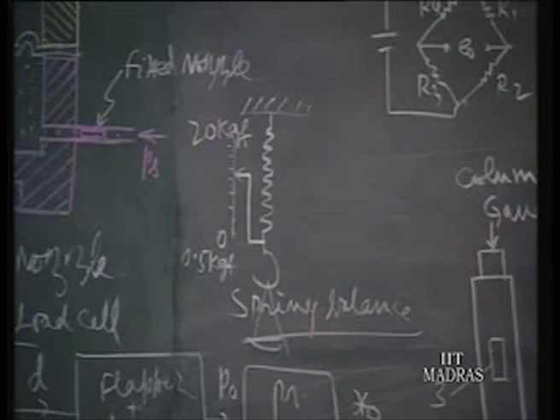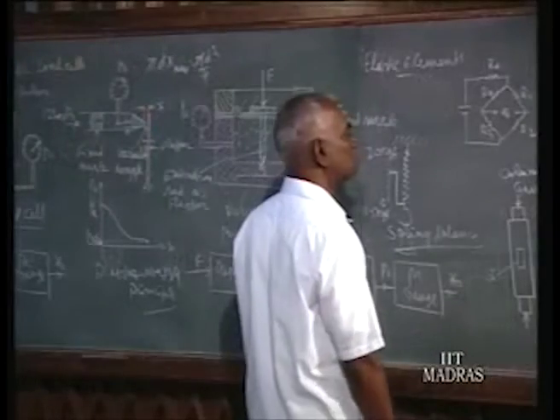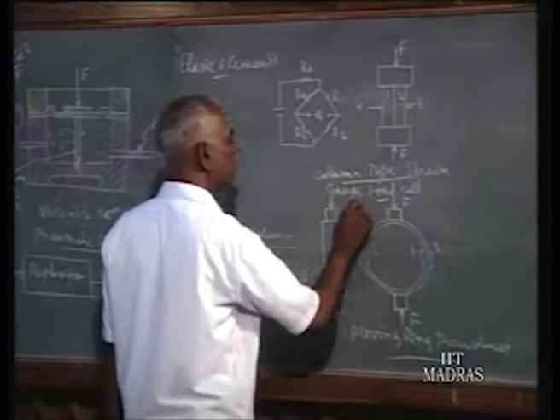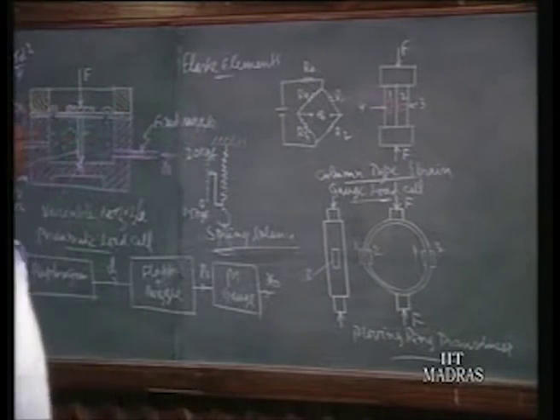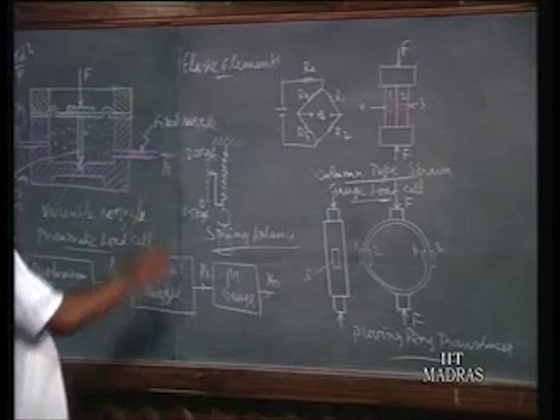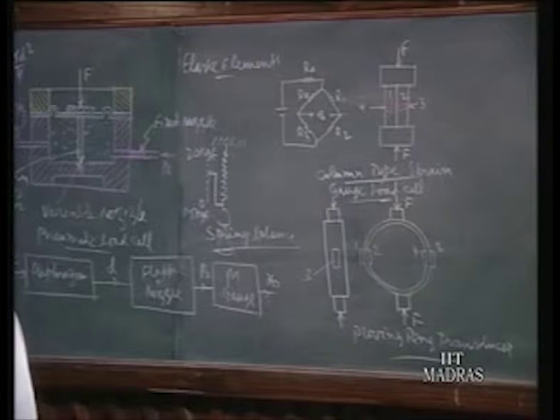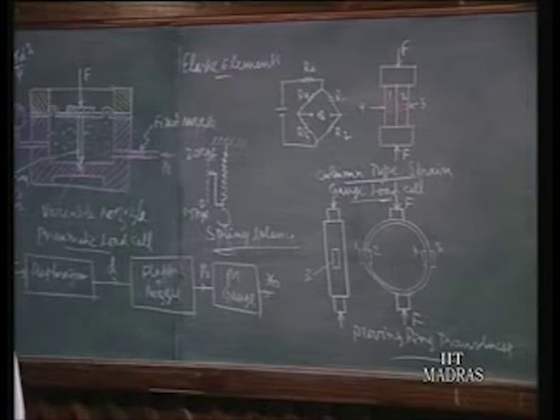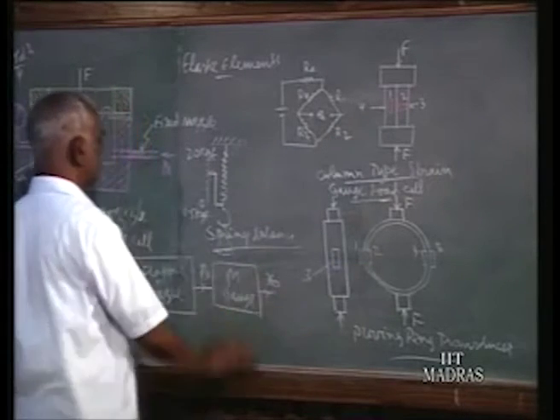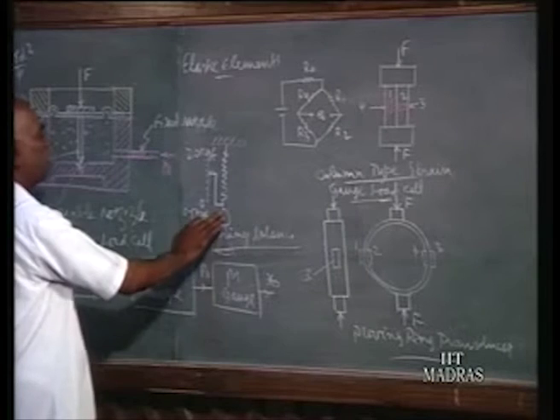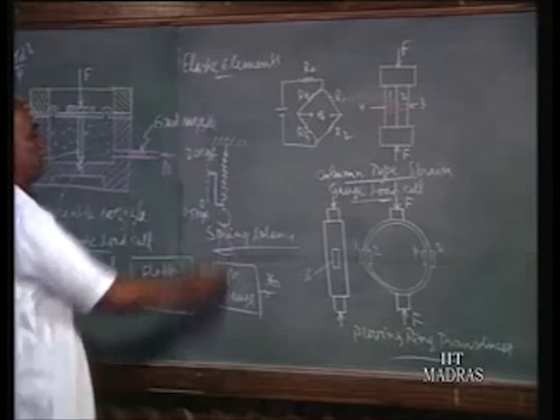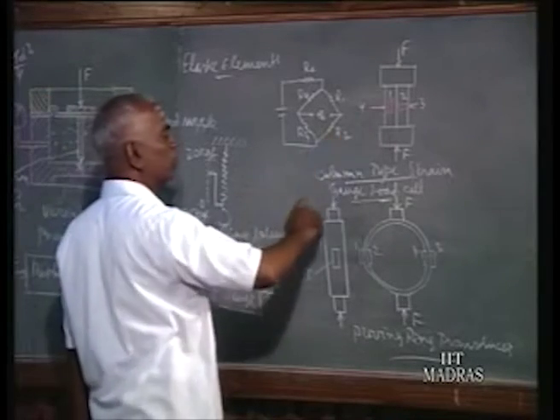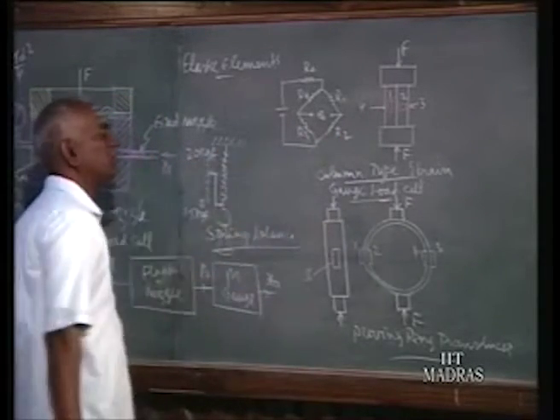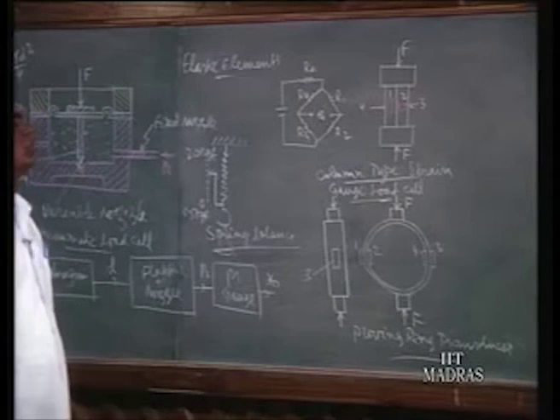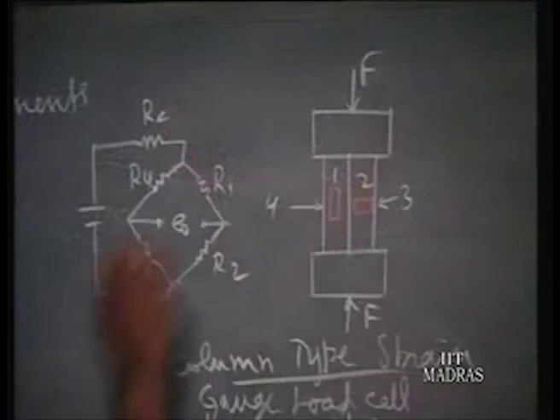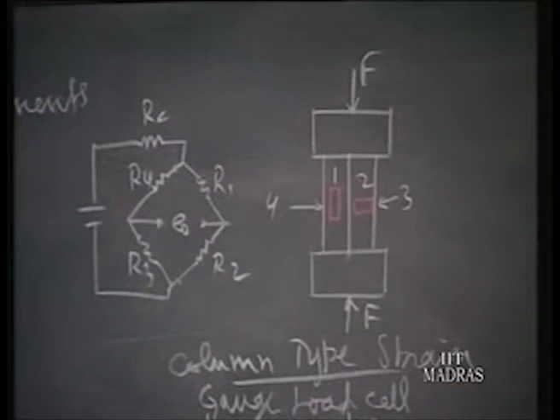The other elastic element, the foremost and often used, is the column type strain gauge load cell. This is very often made use of, and it has fairly high load carrying capacity, up to a few tons we can measure. The main advantage: this spring balance is a purely mechanical instrument, so only static, no dynamic measurements can be made. But in the case of this column type strain gauge load cell, we are converting the mechanical force signal into an electrical signal. So you can use it for both static as well as dynamic measurement. Force can be varying, and still you can measure it.